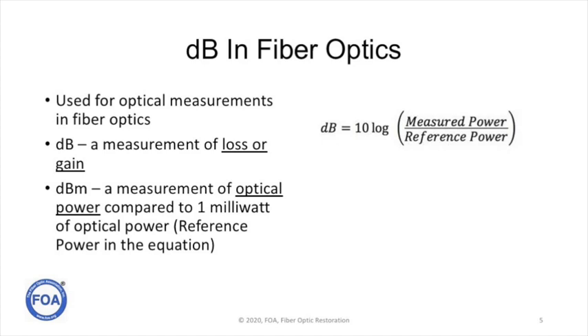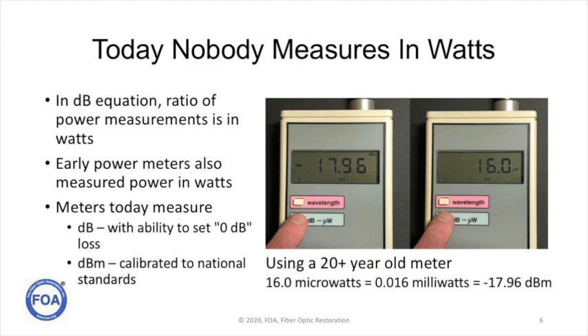We use it in two different ways in fiber optics. We use it just as dB, a measurement of loss or gain, usually the loss or attenuation of a fiber optic cable. And we use it as dBm, which is a measurement of optical power, compared to one milliwatt. For example, for transmitter outputs or receiver inputs.